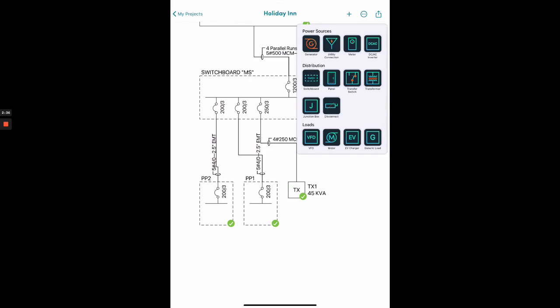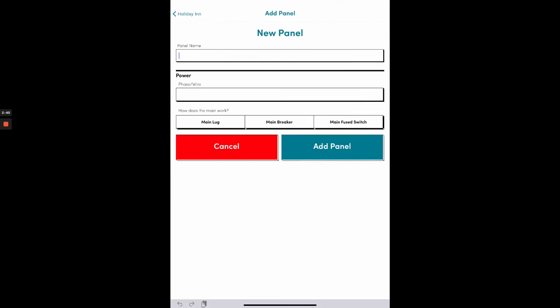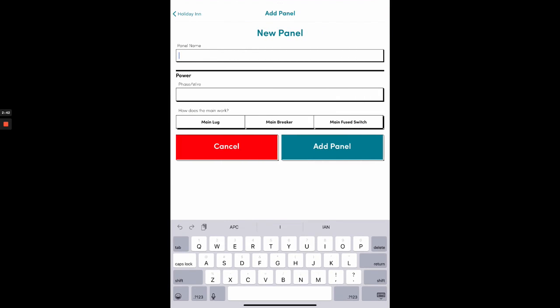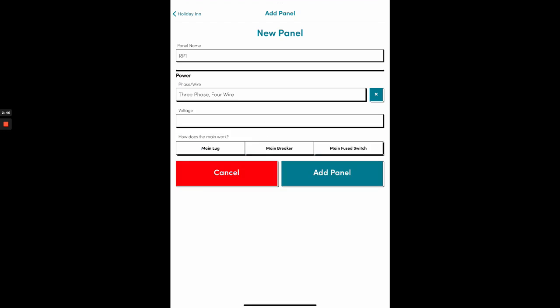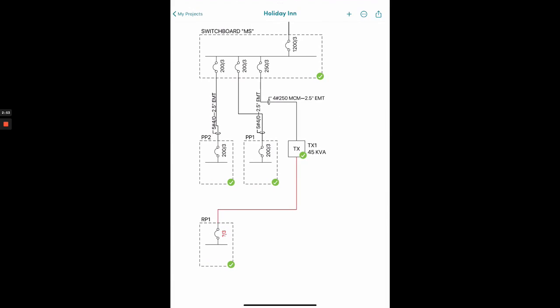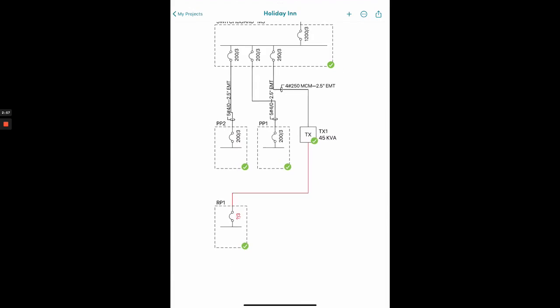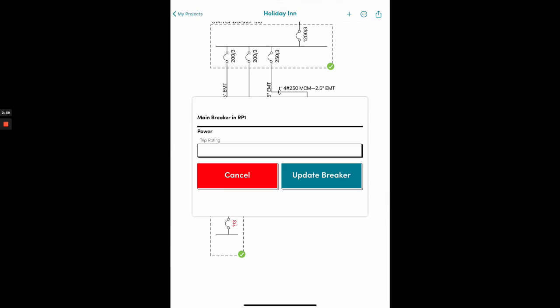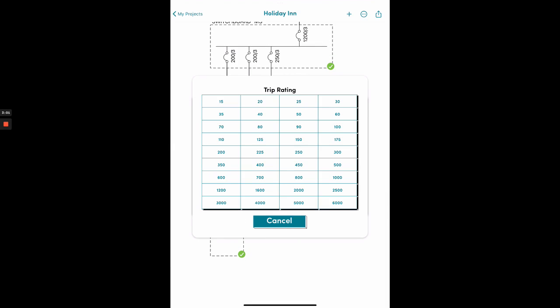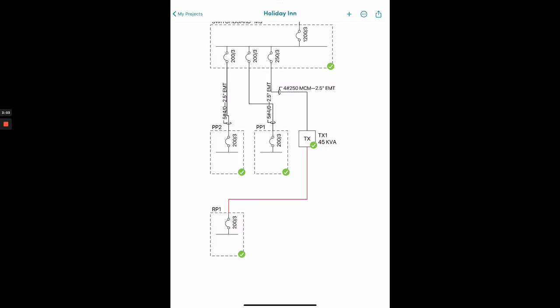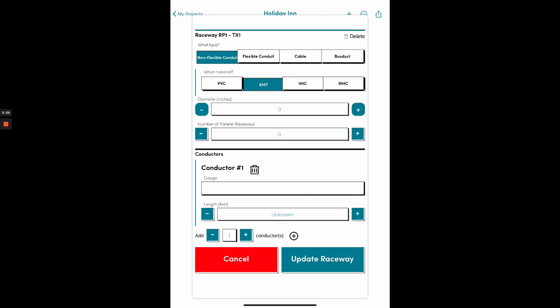That's going to bring up the equipment menu up top, and I'm just going to go ahead and add a panel. And I'm going to call this panel RP1. Phase wire distribution, this is 120/208 because we're on the secondary side of that, and we'll say it's a main breaker. We'll add panel, and it's going to go ahead and create that raceway in the panel downstream of transformer TX1.